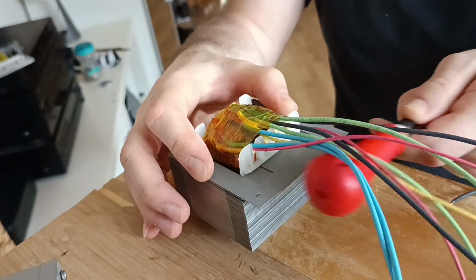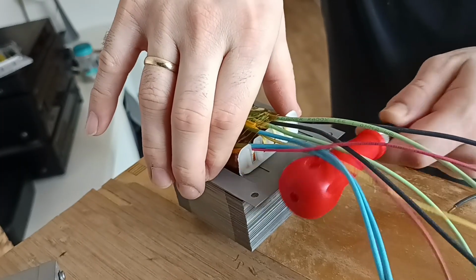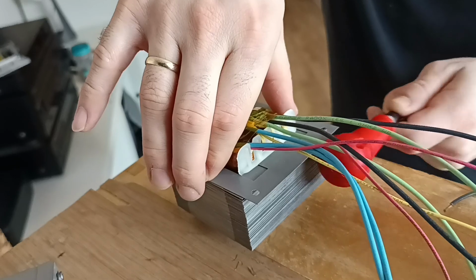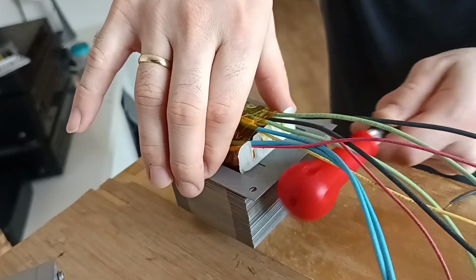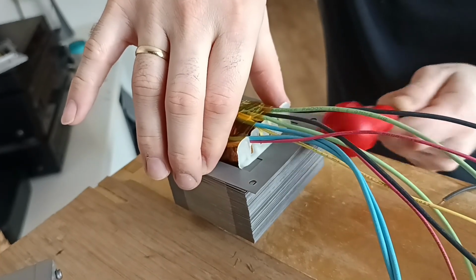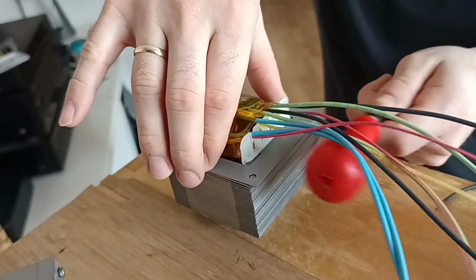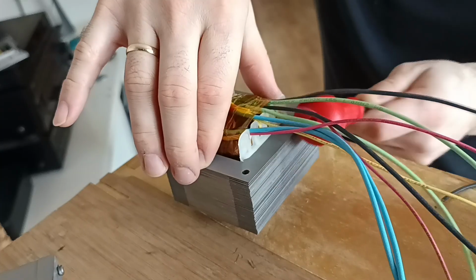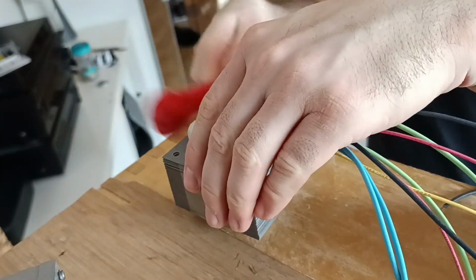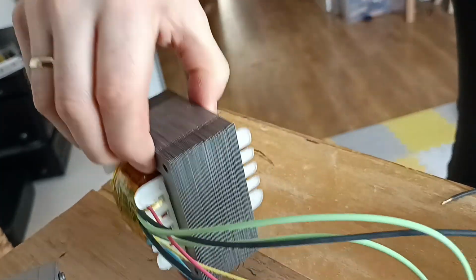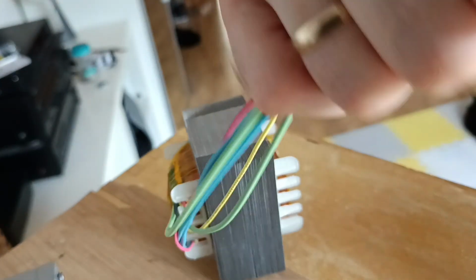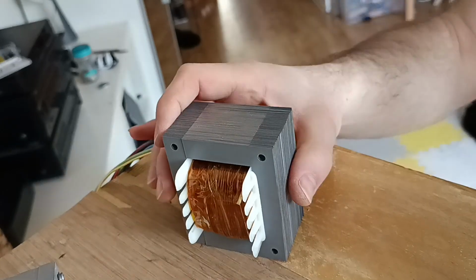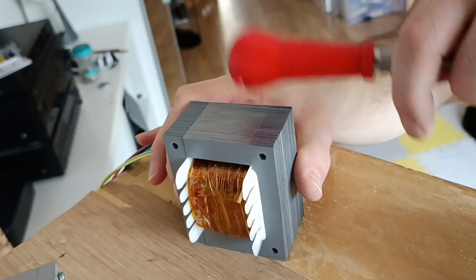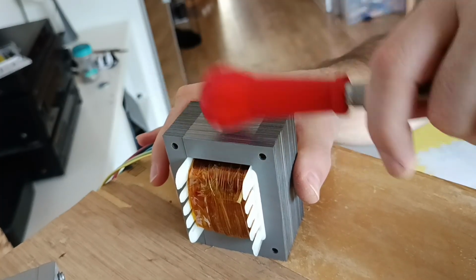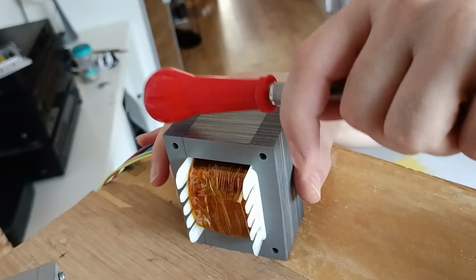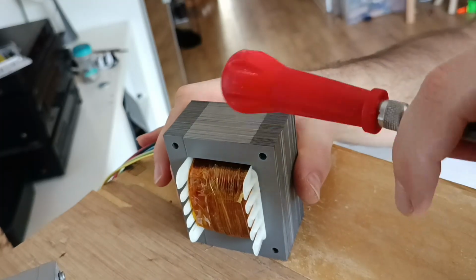You can also bend them, making them unusable since they'll mess up the whole core. So here I'm tapping lightly with the plastic handle of a screwdriver, careful not to bend or destroy the lamination - just lightly tapping from all sides until it fits snugly to the bobbin. Once the whole core is assembled, you also want to even it out by tapping from all sides to get all the laminations aligned and flat before inserting the I laminations into the holes on the sides.